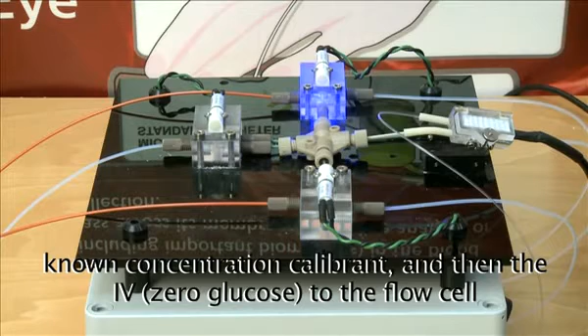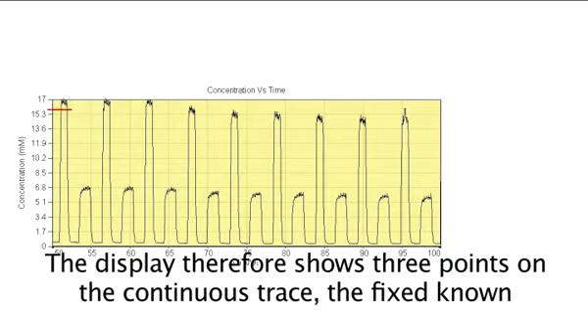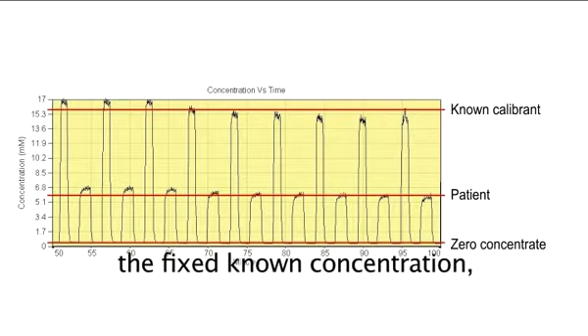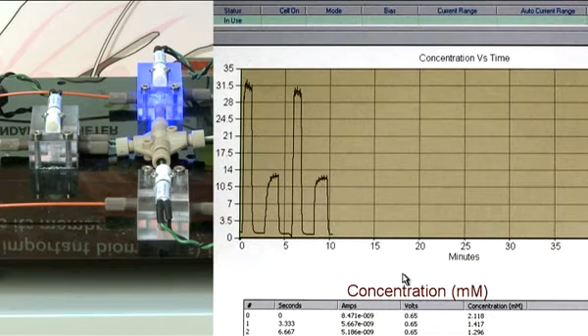Between cycles of perfusate through the MicroEye, the switching valve allows first known concentration calibrant and then the IV, zero glucose, to the flow cell and sensor for auto-calibration. The display therefore shows 3 points on the continuous trace: the fixed known concentration, a zero value and the patient value. This way, if sensor drift or performance changes, then the patient value is automatically recalibrated.